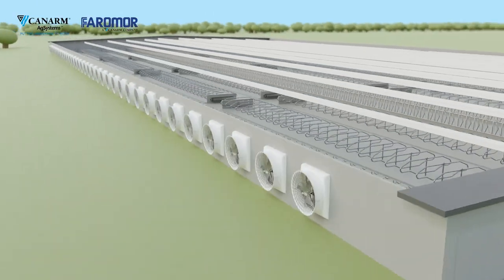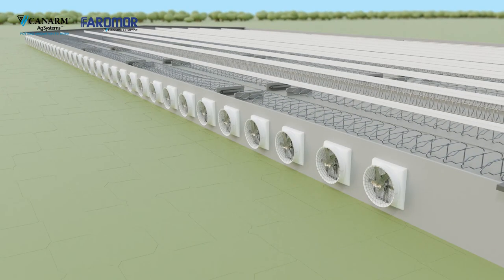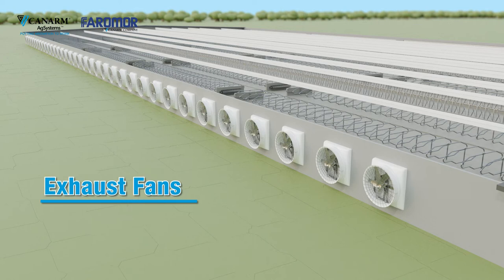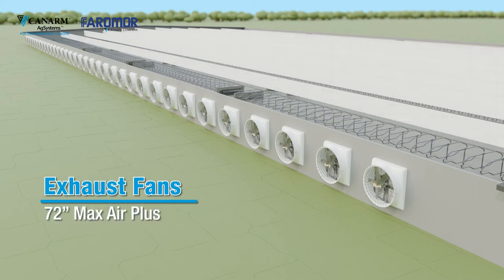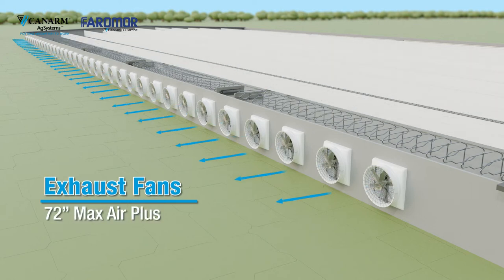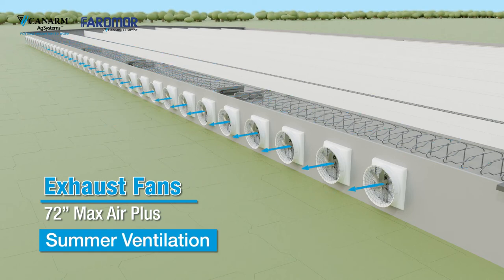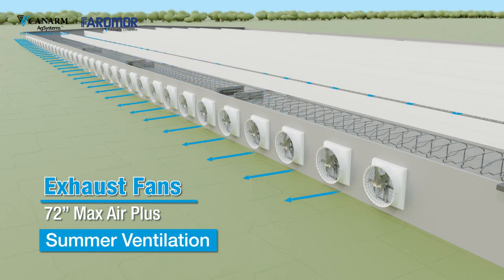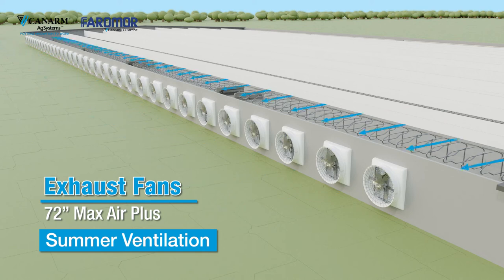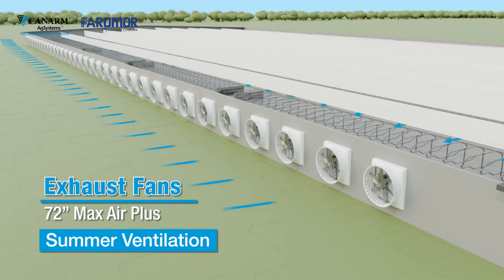On the opposite side of the building are the exhaust fans, which control the building air exchange rate of a cross-flow ventilation system. In the summer, all fans will typically be running at full speed to get the highest air velocity flowing over the cows, providing a minimum complete air exchange rate of approximately every two minutes.